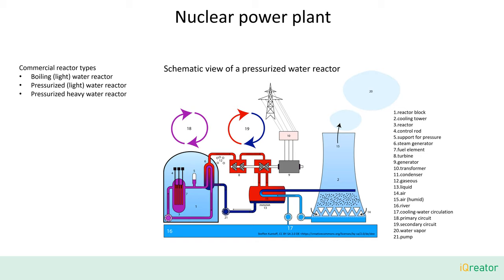Considering reactor designs currently in operation worldwide, one can distinguish between boiling water reactors and pressurized water reactors. Here is a schematic view of a pressurized water reactor. The fuel elements are constantly heating up water in the primary circuit. The heat from the primary circuit is exchanged in a boiler and heats up the cold high-pressure water of the secondary circuit, generating high-pressure steam. The steam is then propelling the turbines, losing temperature and pressure on the way. The turbine is powering the generator, and the cold low-pressure steam needs to be condensed with external cooling water from river, sea, or cooling tower, and then repressurized to close the circle.